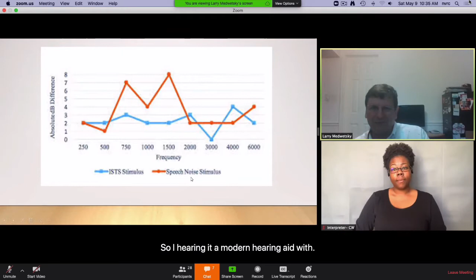So a modern hearing aid with the feature included, in terms of being able to recognize and adapt to the environment, if it recognizes speech in the noise, it leaves it alone and doesn't do very much. It'll cut out the lows because that's where you may not need it, and it may cut out the highs somewhat, but it's trying to maintain the speech alone. So it does not amplify, and does not decrease it much.